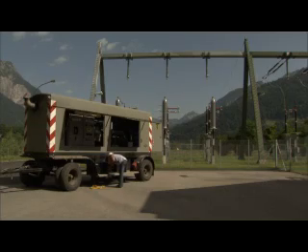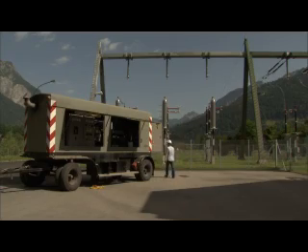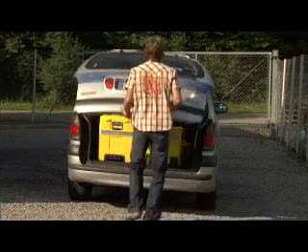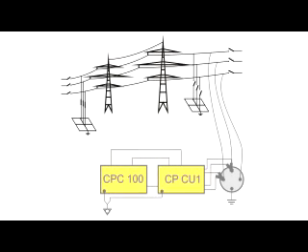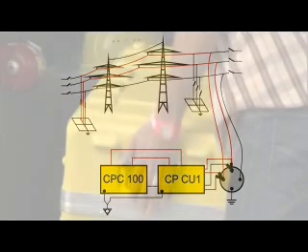Until now, measurements to verify these calculations have rarely been performed due to the excessive effort involved. CPCU1 and CPC100 make these measurements both simple and fast. The line is grounded at the far end. The CPC is connected via the CPCU1 to the overhead line to inject the current. The voltage is measured and impedance and residual compensation factor are automatically calculated.